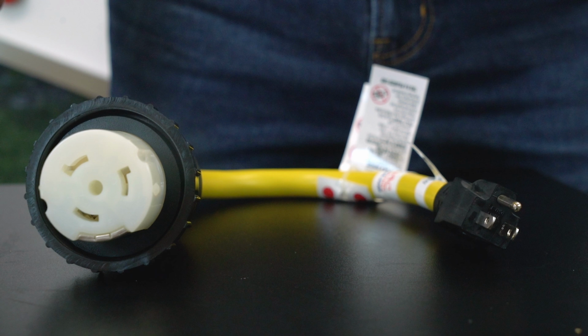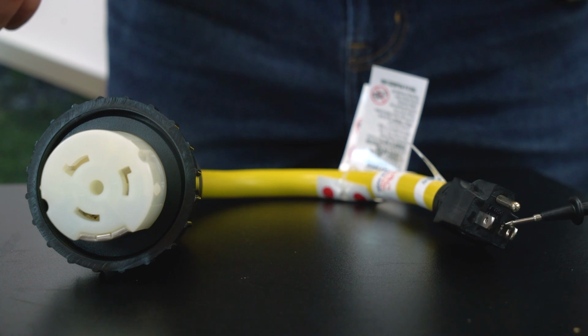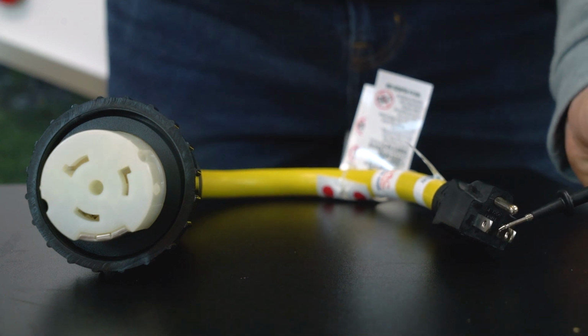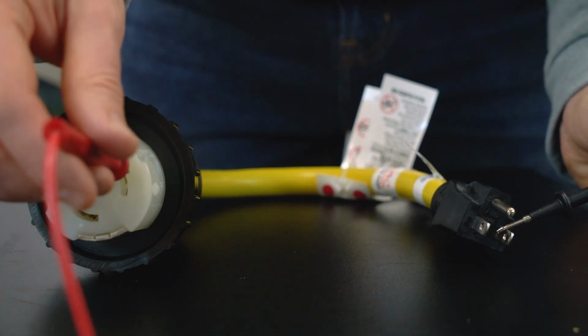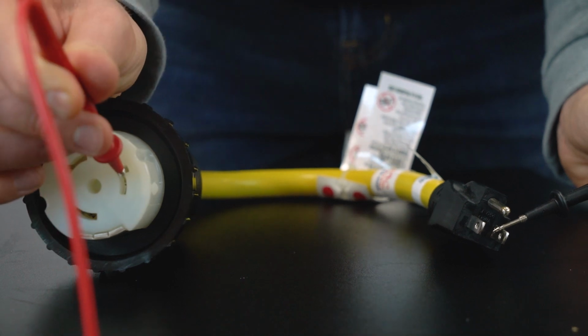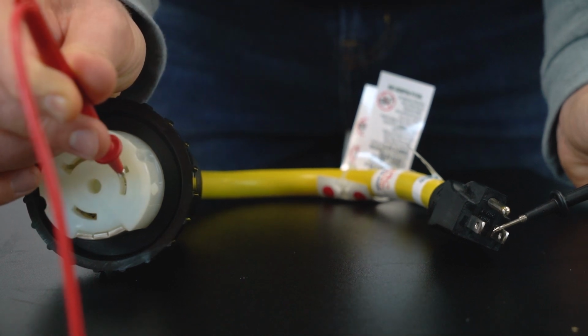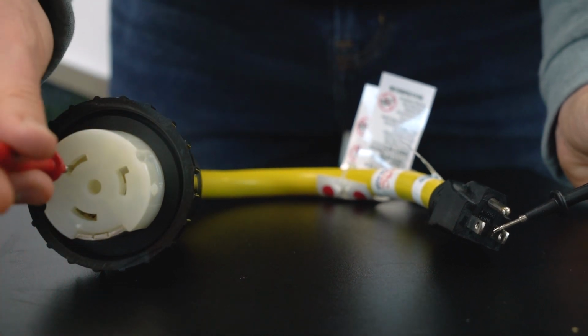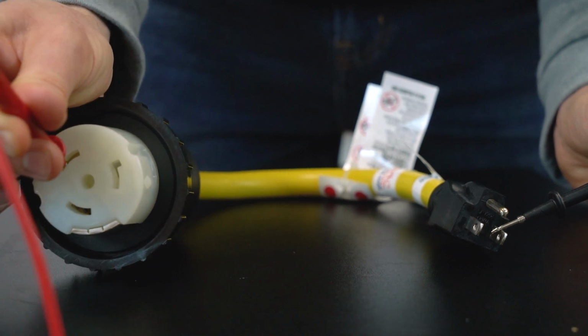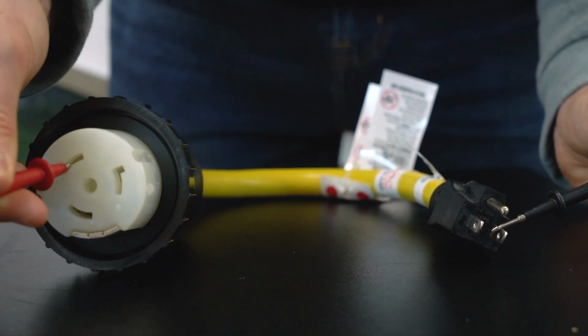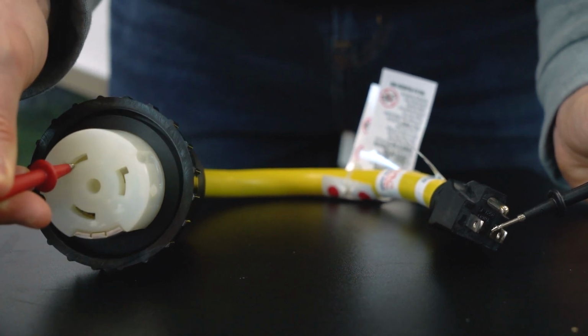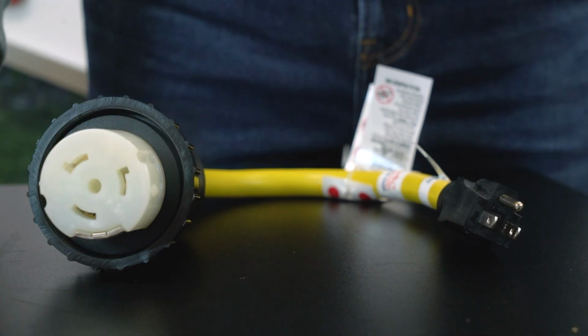Check continuity and bridging of the hots. Because the 515 plug has a single hot and the SS250 connector has two, place one probe on the hot terminal on the 515 side. Use the other probe to check each of the two hots on the SS250 side, one at a time, often labeled X or Y. You should get continuity or a beep on both SS250 hot connections. This verifies the HOTS bridged configuration is working as intended.